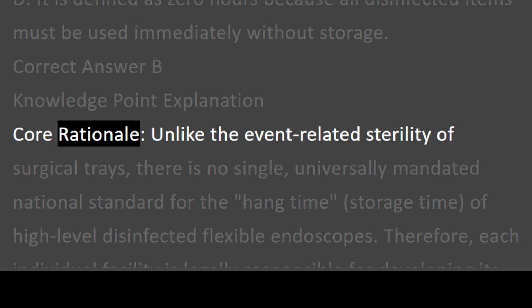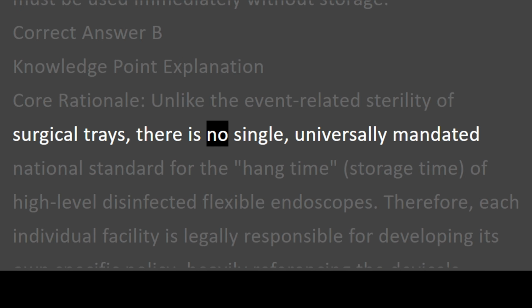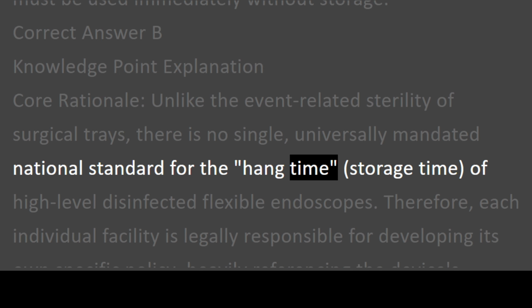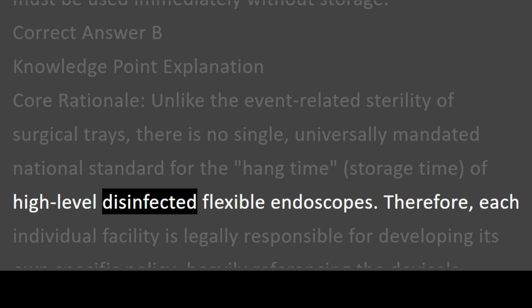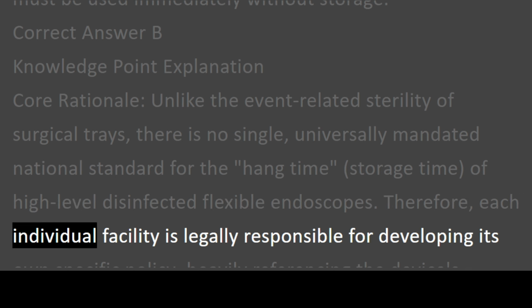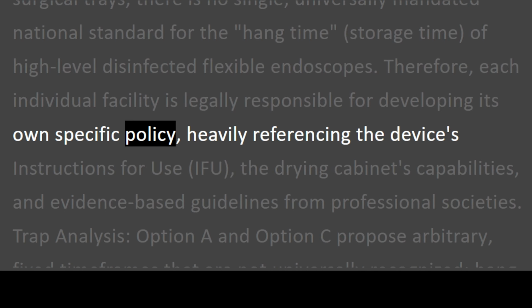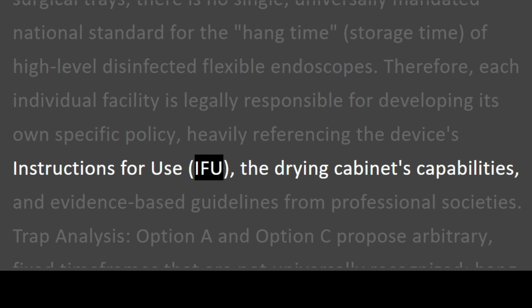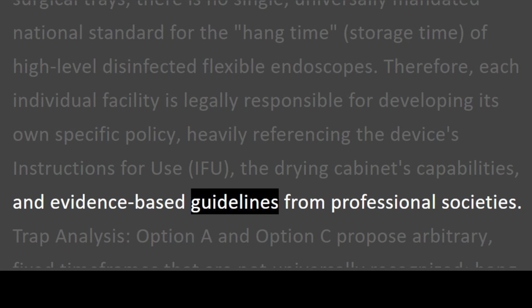Core rationale. Unlike the event-related sterility of surgical trays, there is no single, universally mandated national standard for the hang time, storage time, of high-level disinfected flexible endoscopes. Therefore, each individual facility is legally responsible for developing its own specific policy, heavily referencing the device's instructions for use, IFU, the drying cabinet's capabilities, and evidence-based guidelines from professional societies.